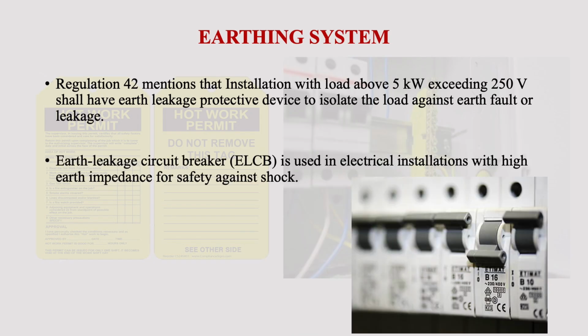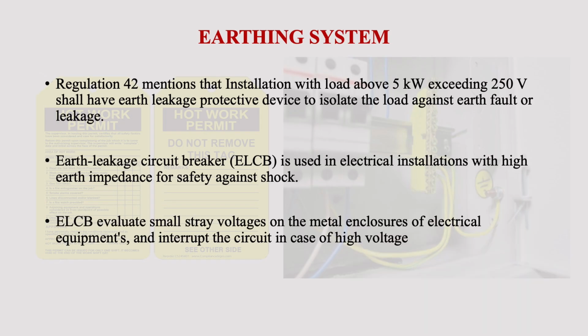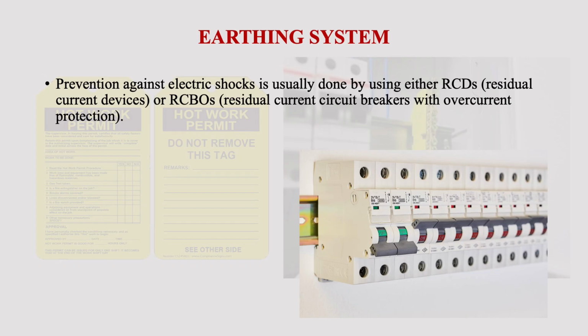An earth leakage circuit breaker, known as ELCB, is a safety device mainly used in electrical installations with high earth impedance for safety against shock. ELCBs evaluate small stray voltages on the metal enclosures of electrical equipment and interrupt the circuit in case of high voltage. Whatever the source of earth leakage, it must be prevented from causing electric shock.